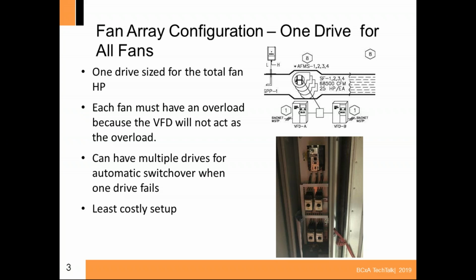We try different ways to verify fan operation, and I don't like doing it from the drive. I'm just a keep-it-simple kind of guy, and I always want them to put the CT on the overload. If I've got power going to the fan, then I have to make the assumption that the fan is on. On the motorized dampers, I also request a feedback signal, an open/close limit switch, so we know when that damper is open.